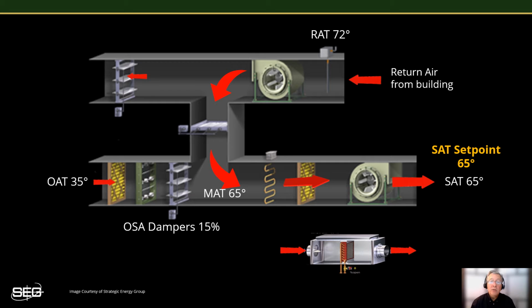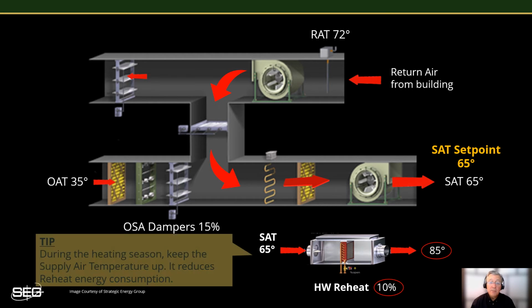So we've managed to raise the supply air temperature 10 degrees, from 55 to 65 degrees, and without any supplemental heating needed from the air handler's heating coils. Now, let's look and see what's happening out at the terminal unit. The terminal unit is now receiving that 65-degree supply air, and the hot water reheat valve has now dropped to only 10% open, where previously it had been maintained at 60% open. Yet the terminal unit is still able to supply the 85-degree air needed to maintain the zone at set point. So this little change in supply air temperature can result in using much less reheat energy throughout the whole system.